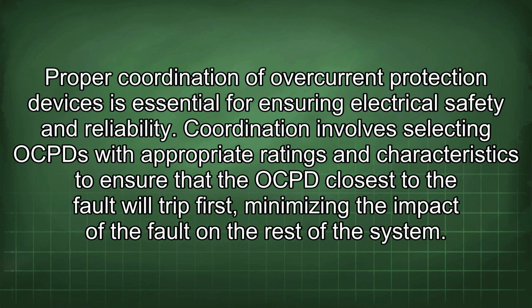Proper coordination of overcurrent protection devices is essential for ensuring electrical safety and reliability. Coordination involves selecting OCPDs with the appropriate ratings and characteristics to ensure that the OCPD closest to the fault will trip first, minimizing the impact of the fault on the rest of the system.